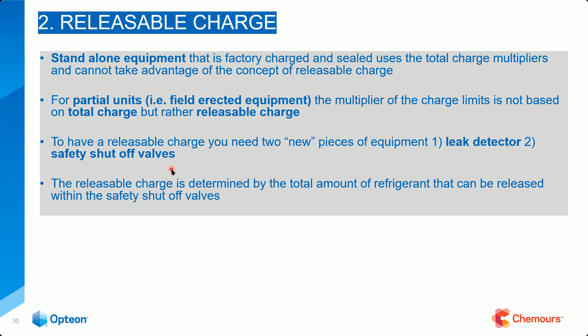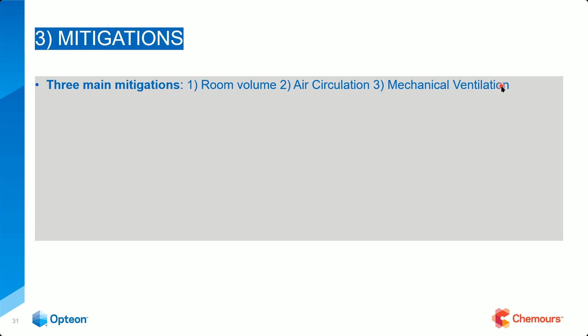The third part is mitigation strategies. There are three main mitigations. First of all, room volume in cubic feet. Second, will we need air circulation? And third, will we also need mechanical ventilation? In some cases, you'll need both air circulation and mechanical ventilation. When we say air circulation, all that's saying is kicking on the evaporator fans if there is a leak, to lessen the concentration in one space. But mechanical ventilation is literally either removing the air or bringing fresh air in, and we'll walk through that one by one.